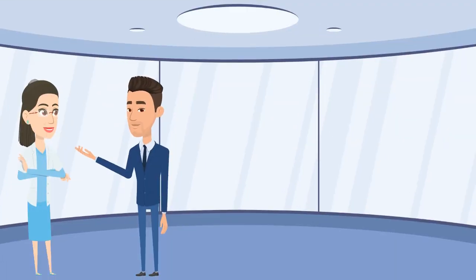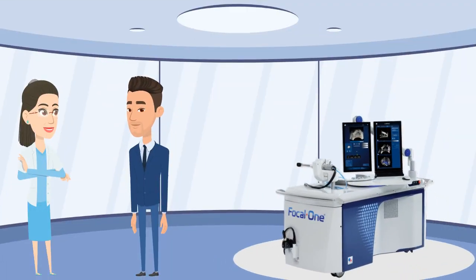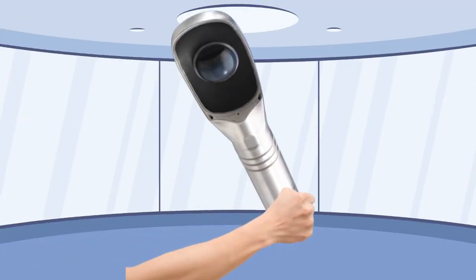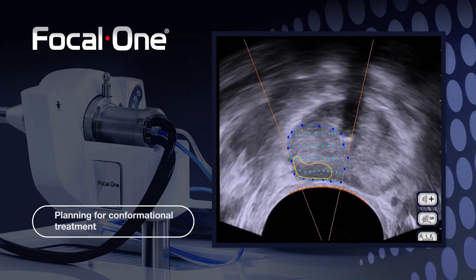This is the Focal One. As you can see, it is a single, integrated unit with a small footprint. It can be easily moved between ORs or to a storage location between cases. This is the endorectal probe. This is one of the key components of our technology. The probe has a 7.5 MHz imaging transducer and a treatment transducer made up of 16 concentric rings. The design allows for the quick and accurate application of energy to the desired target.